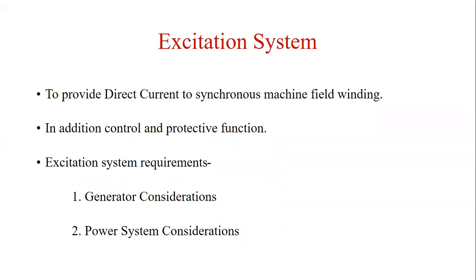The basic function of an excitation system is to provide direct current to the synchronous machine field winding. In addition, the excitation system performs control and protective functions essential to satisfactory performance of the power system by controlling the field voltage and thereby the field current. The control function includes the control of voltage and reactive power flow and the enhancement of power system stability as well. The protective functions ensure that the capability of the synchronous machines, excitation system and other requirements are not exceeded.